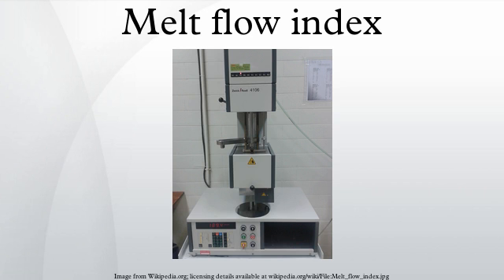The weight exerts a force on the molten polymer and it immediately starts flowing through the die. A sample of the melt is taken after the desired period of time and is weighed accurately. MFI is expressed in grams of polymer per 10 minutes of duration of the test.